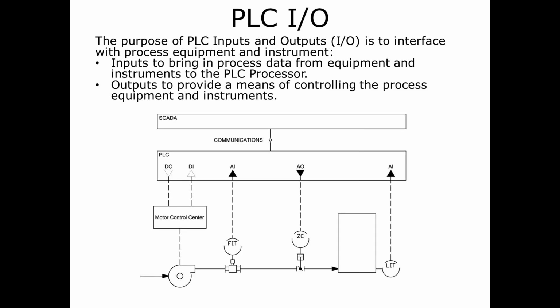Okay. Hey, thanks, Molly. So moving on, we're going to talk a little bit about PLC I/O. I/O is inputs and outputs, and that is what's used to interface between the equipment and the instruments. Inputs basically bring the process data into the PLC processor from the equipment and the instruments, and outputs provide a means of controlling the process out to the equipment and instruments. Usually inputs are coming in from the instruments, and outputs are what's going out to the equipment.